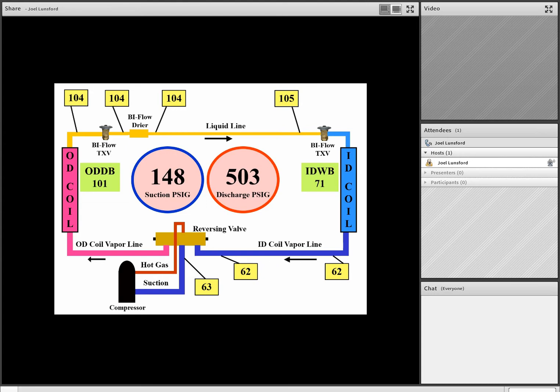Let's take a look at the subcooling on the warm coil. As we take a look at our pressure temperature conversion for R410A at 503 pounds of pressure, we see that gives us about 134 to 135 degrees. As we take a look at the temperature leaving the warm outdoor coil in this example, we have a 104 degree liquid line temperature. Well, 503 pounds of pressure is equal to 134 degrees. So we have 30 degrees of subcooling on the outdoor coil.